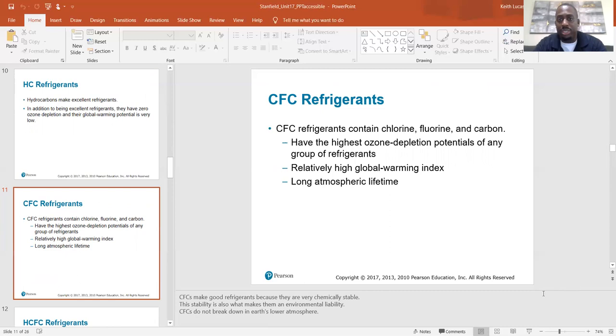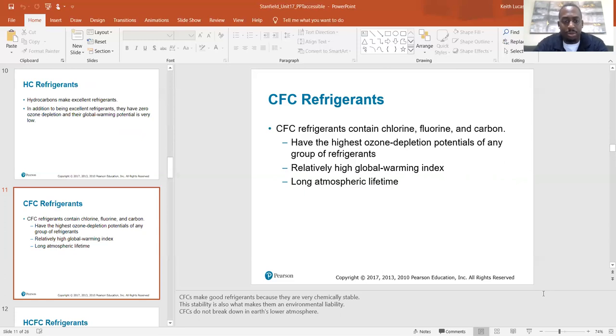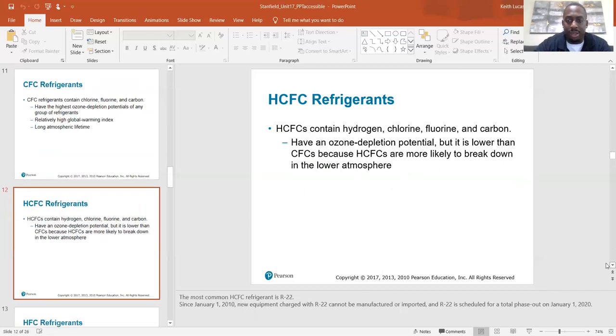CFC refrigerants contain chlorine, fluorine, and carbon — making them chlorofluorocarbons — and have the highest ozone depletion potentials of any group of refrigerants. They also have a relatively high global warming index and long atmospheric lifetime. CFCs make good refrigerants because they are very chemically stable, but this stability is also what makes them an environmental liability. CFCs do not break down in the Earth's lower atmosphere — rather than breaking down, they break down the ozone layer.